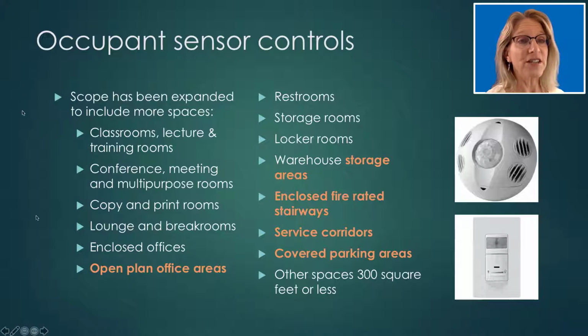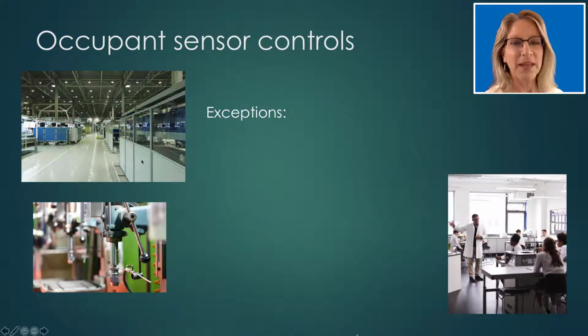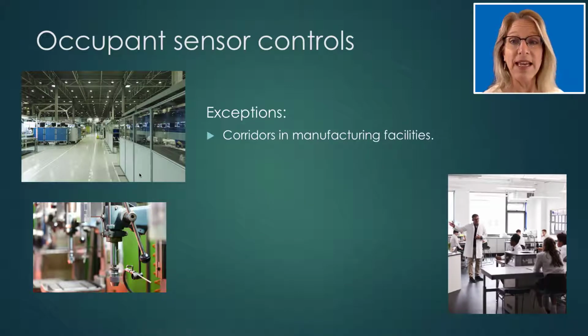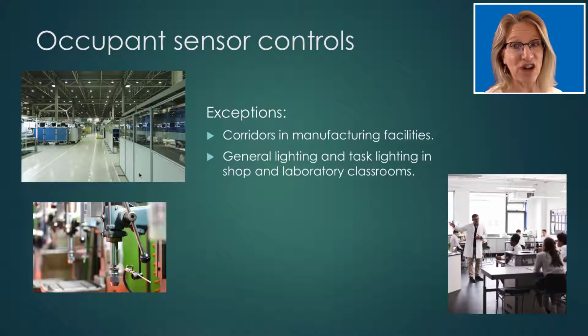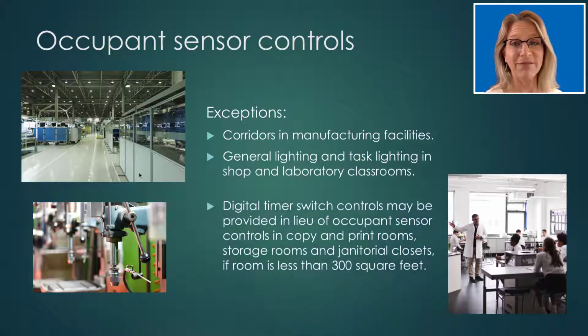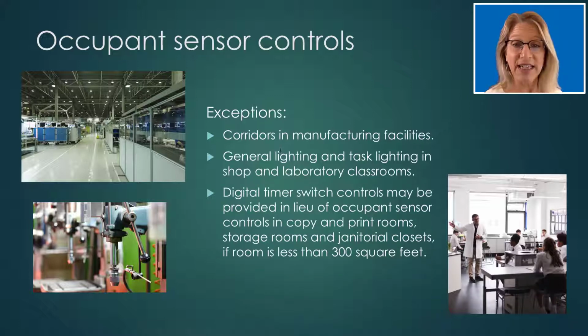This list here shows all of the spaces that are required to have occupant sensor controls, and the ones highlighted in orange are those that are new. So it's now required in open plan office areas, in enclosed fire-rated stairways, service corridors, and in covered parking areas. Also note that there was an adjustment for warehouses, where it has now been clarified that it's only required in warehouse storage areas. Exceptions to this requirement include corridors in manufacturing facilities, and general lighting and task lighting in shop and laboratory classrooms. These spaces are exempt from the occupant sensor control requirement due to safety concerns. In addition, digital timer switch controls may be provided in lieu of occupant sensor controls in very small spaces that are less than 300 square feet.